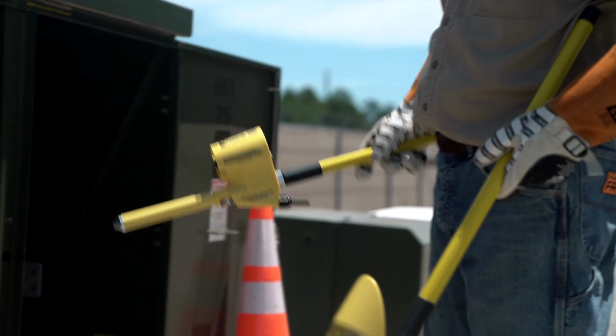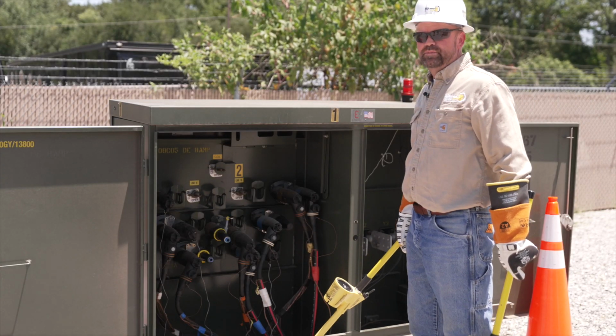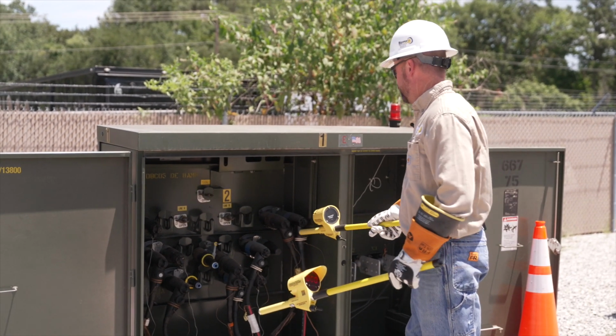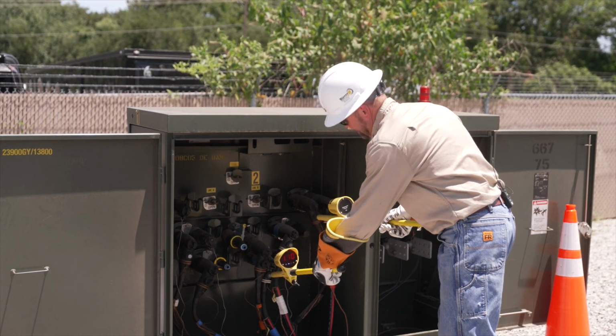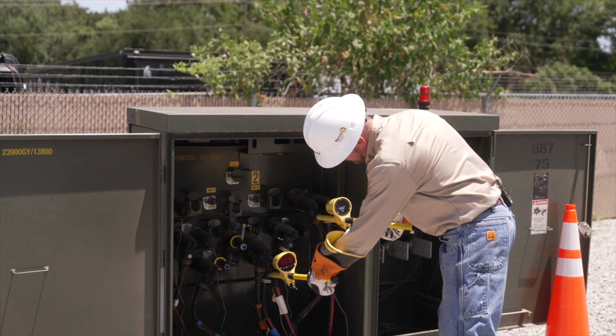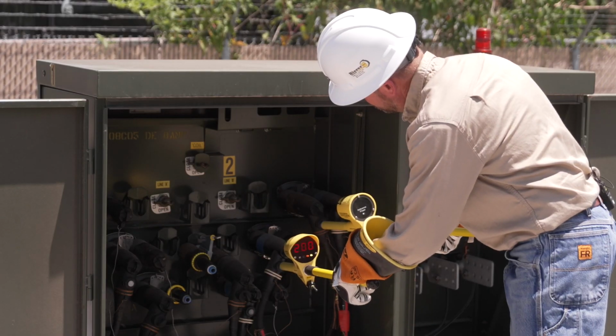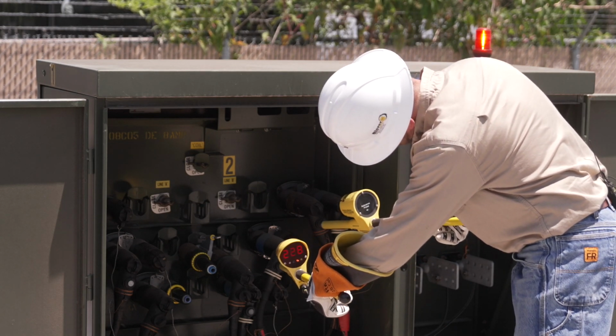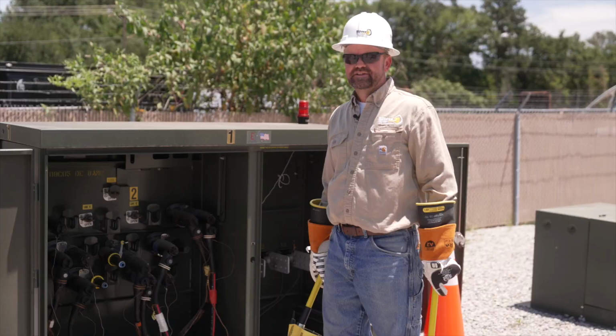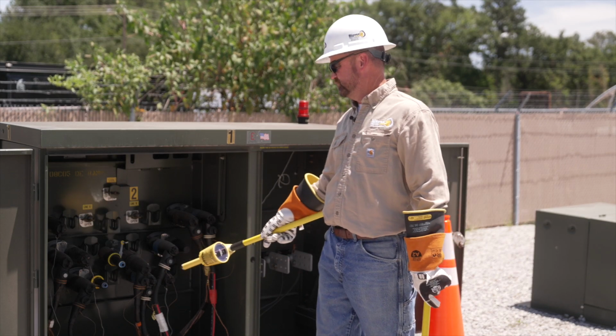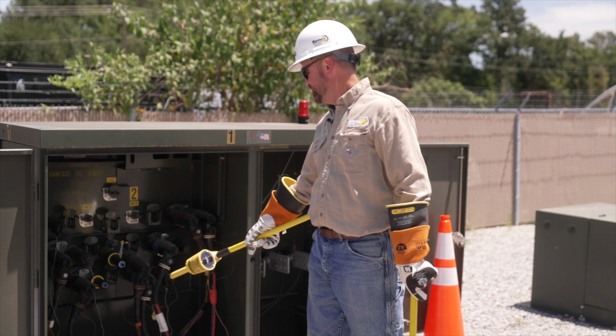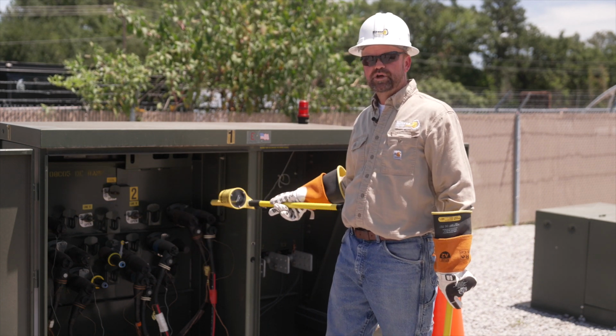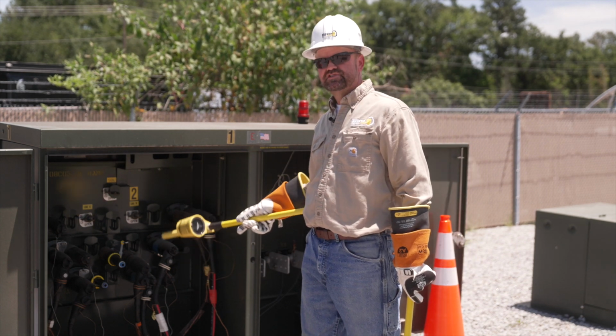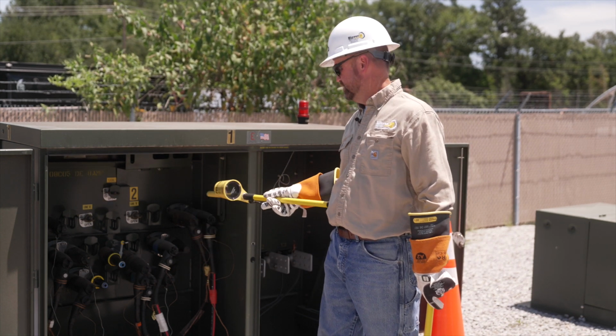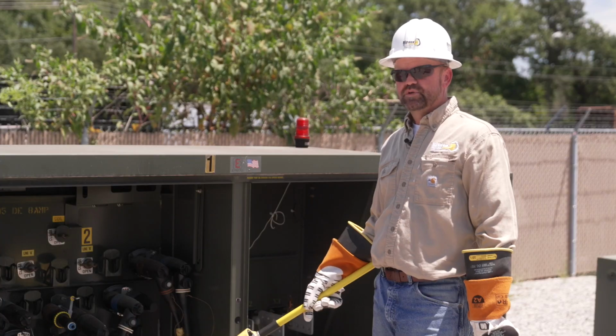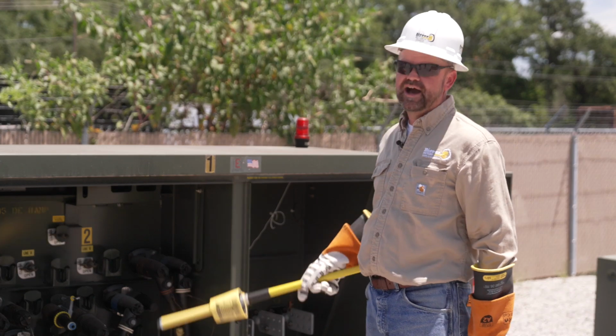So now I can begin phasing now that I know they're energized. So my reference probe is on my H1B. My meter probe is on the H3B. And I get 120 degrees out of phase, my blue light. Put the meter probe on my H2B. I get a red light in near 240 degrees. So having taken the readings, I know my sequence is from bottom to top. In other words, H3B leads H2B leads H1B. So the 120 degrees leads 240 degrees, 240 degrees leads 0, or my reference phase. So again, my sequence is from bottom to top.